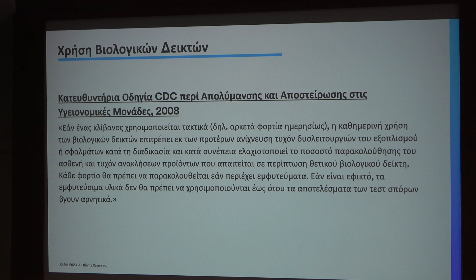I have mentioned this standard. It's important, it will be published, it is revised, but it is also carrying the same messages about using sterilization methods. And the CDC is also explaining about using biological indicators. And for sure, all international and national guidelines agree that implant objects should be monitored with an additional biological indicator, and therefore, before they get the result, it shouldn't be released to the OR.